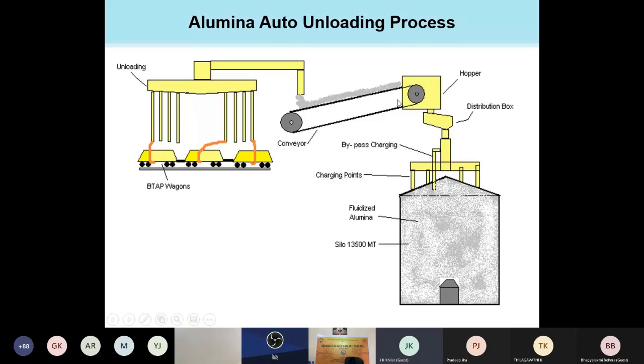PLC is a centralized system. That is, if the valve opening indication is coming, then only the conveyor belt will start. If the conveyor belt running indication comes to the PLC, then the compressor will start. This type of logic is inside the PLCs, and here the only thing the operator does is select to which silo I have to fill the alumina powder.